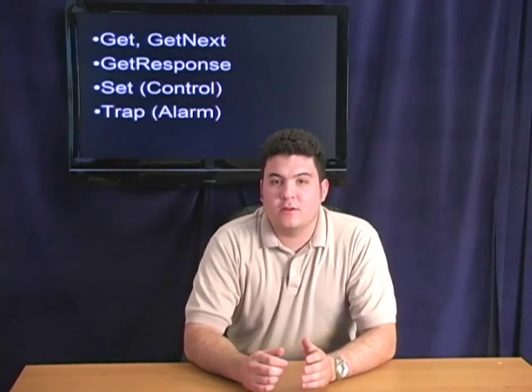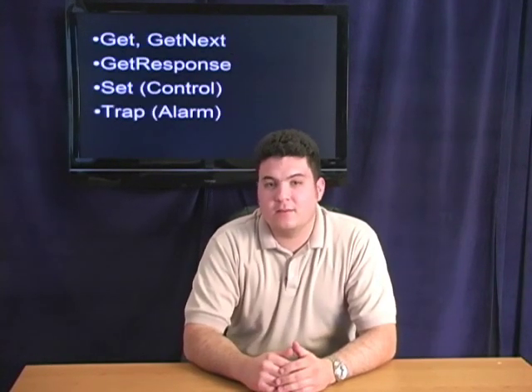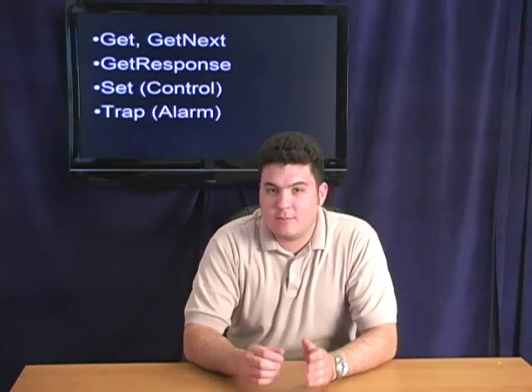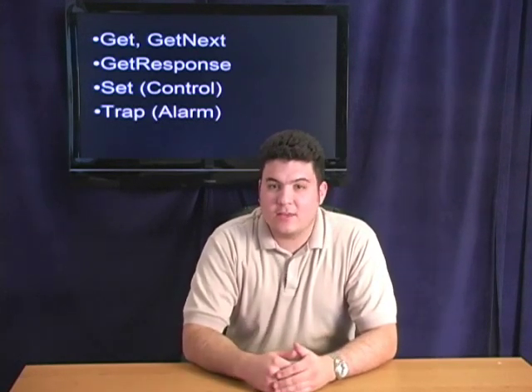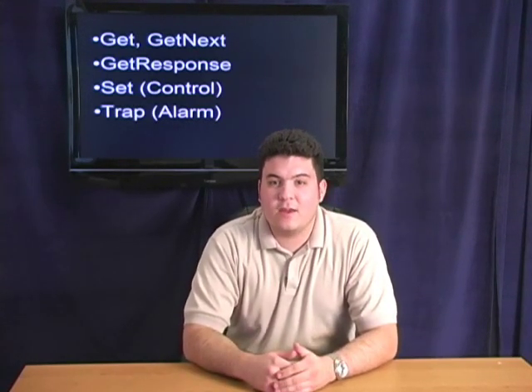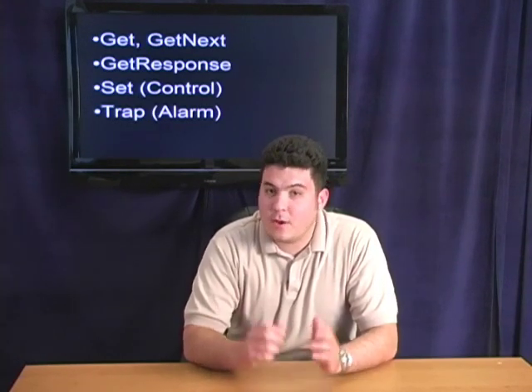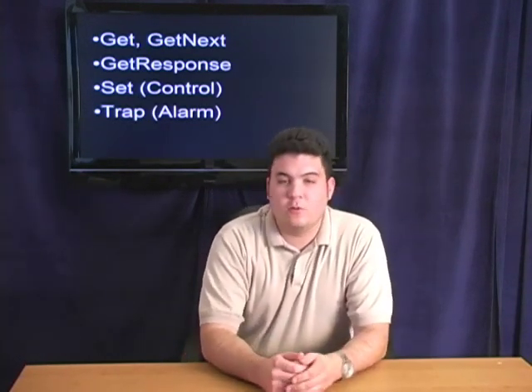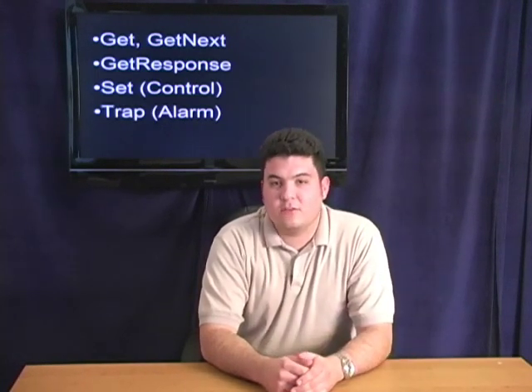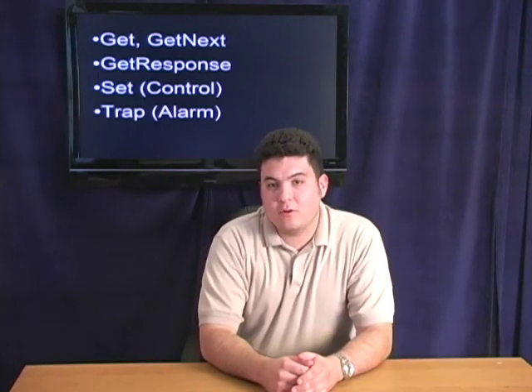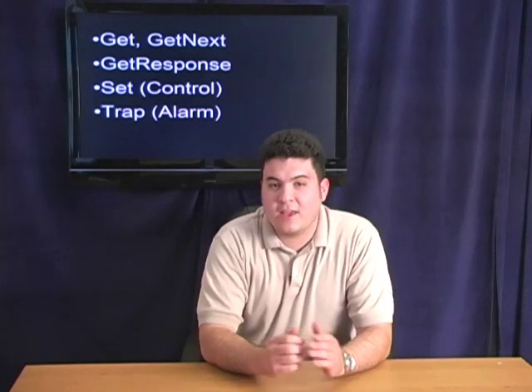Now let's look at how SNMP managers handle alarm messages. SNMP uses just a few basic messages — including GET, GET NEXT, GET RESPONSE, SET, and TRAP — to communicate between the manager and the agent. The GET and GET NEXT messages allow the manager to request information for a specific variable. The agent, upon receiving a GET or GET NEXT message, will issue a GET RESPONSE message to the manager with either the information requested or an error indication as to why the request cannot be processed.